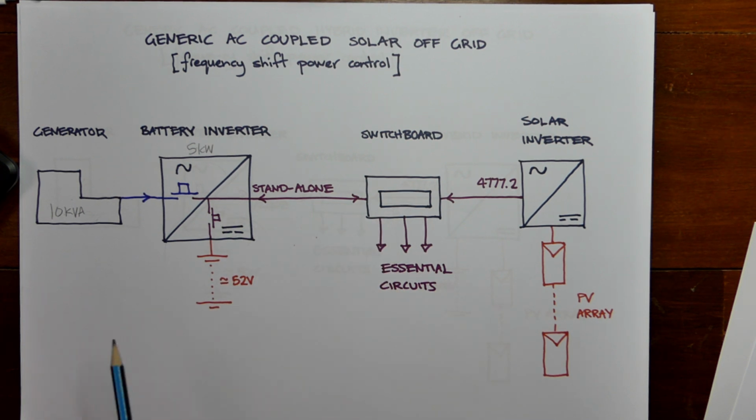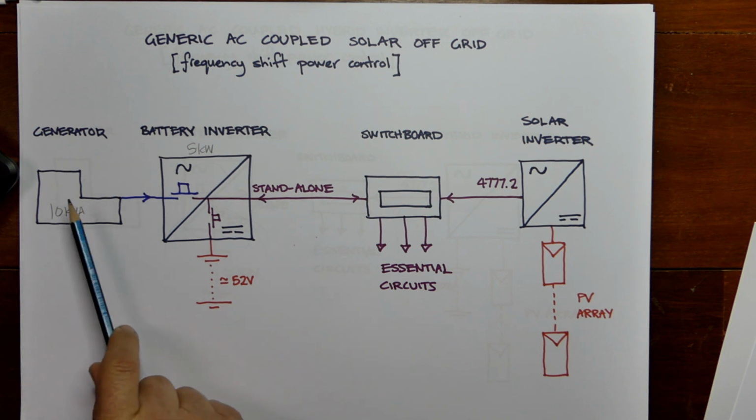So you've actually got the perfect way of using a generating set, particularly a diesel generating set, which is they'll run at a constant load. They're not going to be seeing loads go up and down and the horrors of light loading, which causes significant issues with generating sets. So that's a little bonus.